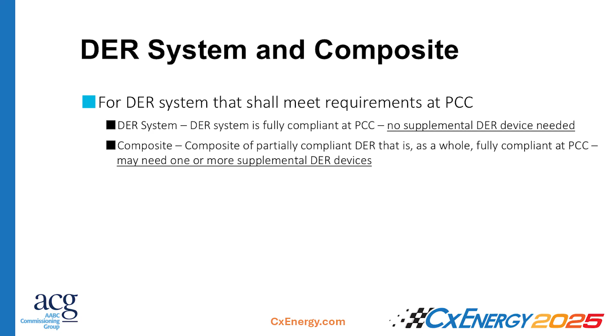So how does this apply to everything you're doing day to day, whether it's V2G or not? If you have a generator that is ever paralleled, in many, if not most, jurisdictions in the US and many worldwide, IEEE standard 1547 is applicable. So these requirements are essential that they're confirmed. If they're not confirmed, depending on the contract, you may not be in compliance with the utility interconnection agreement.